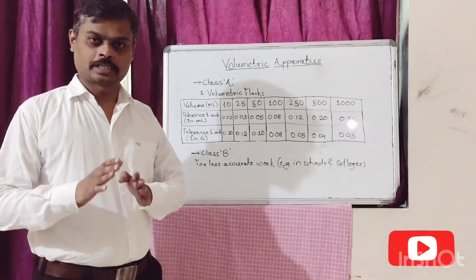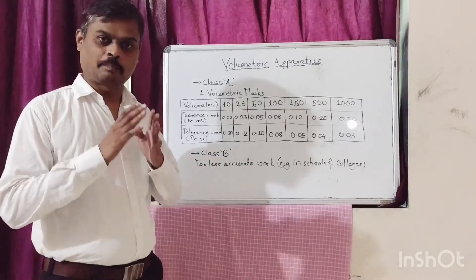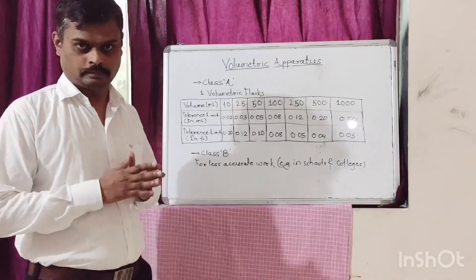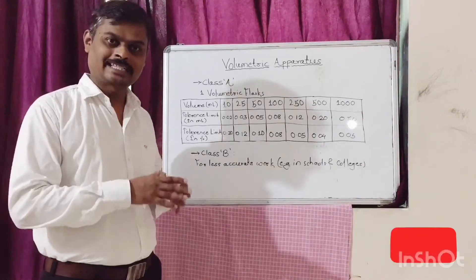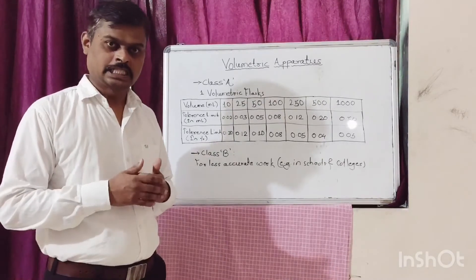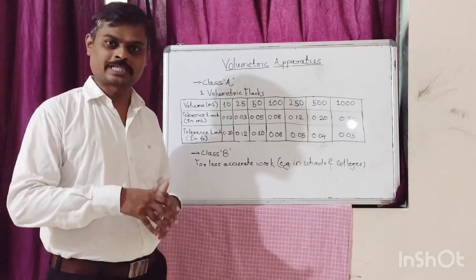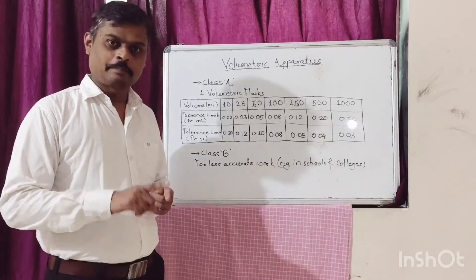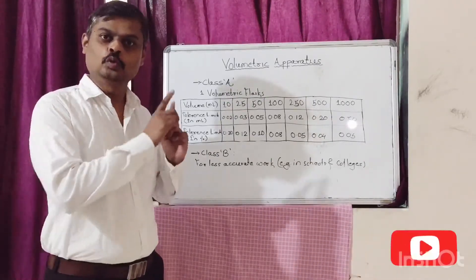The second type of volumetric apparatus is Class B. Class B volumetric apparatus are not recommended for quantitative analysis; these apparatus are generally recommended for less accurate work. They are generally used in schools and colleges for demonstration purposes. Class B apparatus require in-house calibration before putting them into use.